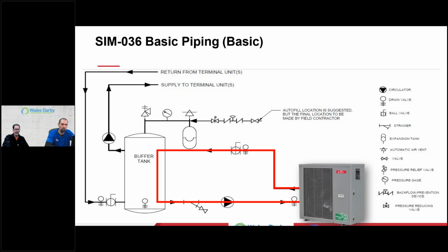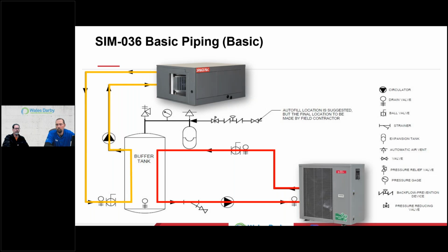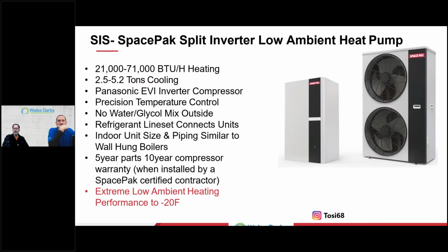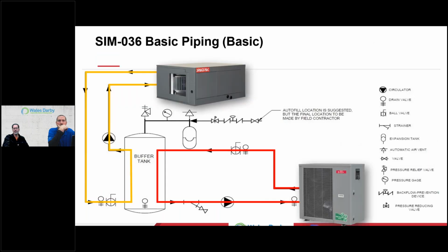Sealed refrigerant, electric-based compression, producing really hot gases that transfer into water, storing that in a buffer tank, and then using that buffer tank to satisfy the loads, the zone, the building envelope, okay? Making people comfortable. That's the game. All right, this is our split. We won't be bringing water. Let me just back up here, and I just want to say at this particular point, if you notice, that outdoor unit will be out in the ambient, and it could be quite cold. So we are not bringing water outside, okay?